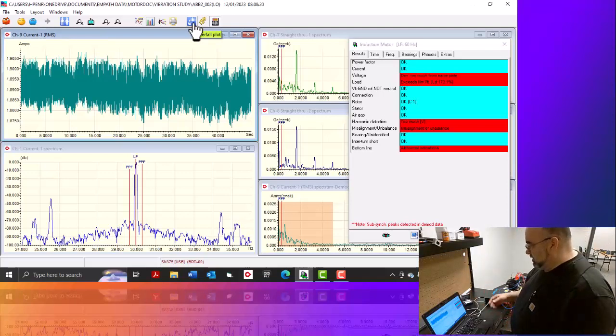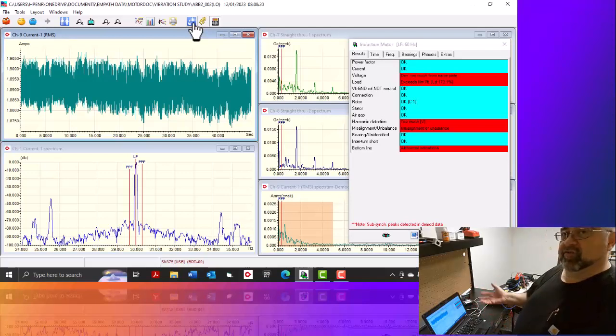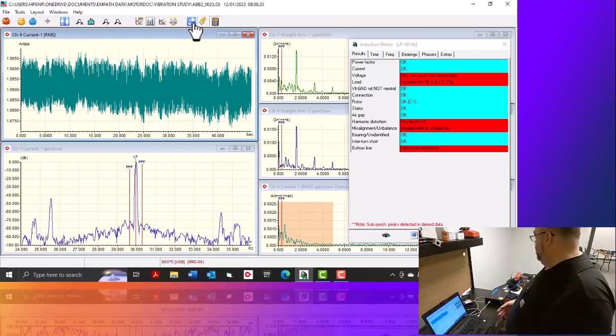However I had it set up, it's telling me it's exceeding the load, probably because it's a high current when I'm at 30 hertz. So it's overloaded for 30 hertz, primarily because of some other conditions, including a little bit of unbalance and some other things going on.